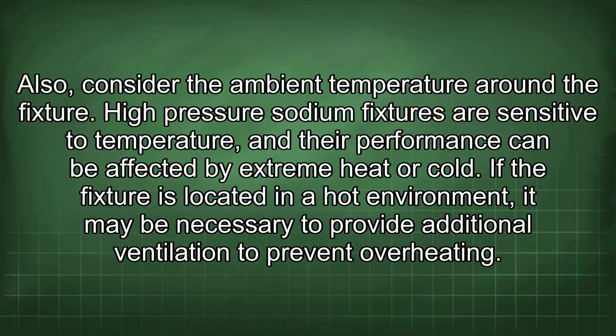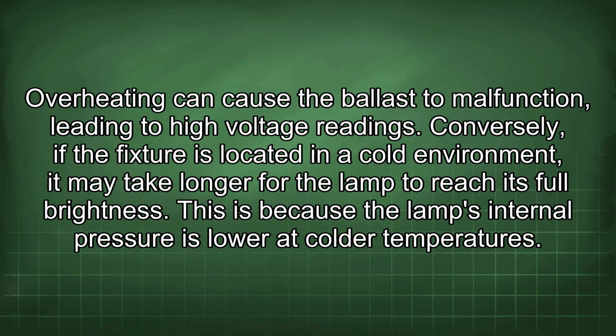Also, consider the ambient temperature around the fixture. High-pressure sodium fixtures are sensitive to temperature, and their performance can be affected by extreme heat or cold. If the fixture is located in a hot environment, it may be necessary to provide additional ventilation to prevent overheating. Overheating can cause the ballast to malfunction, leading to high voltage readings.